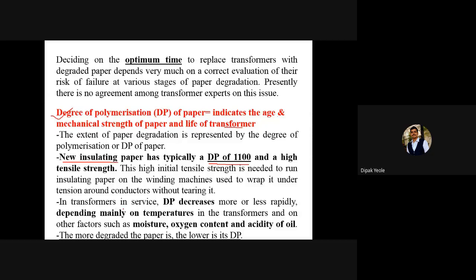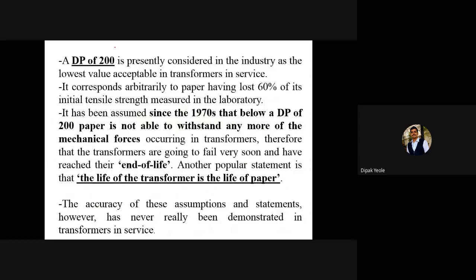But as the transformer is in service, the DP decreases. Why? As the DP decreases, it means our paper is degrading. There is an important statement about this: the more degraded the paper is, the lower its DP, degree of polymerization. Now, whenever the DP value is less than 200, we have to replace this paper accordingly.